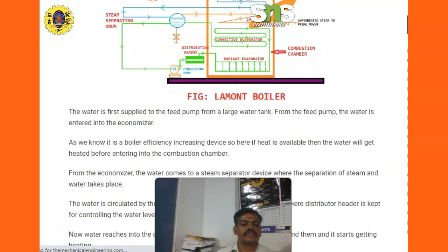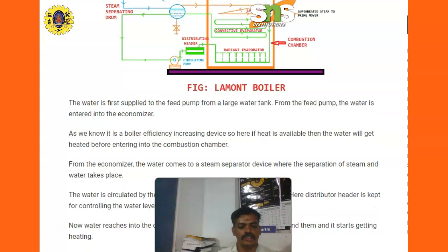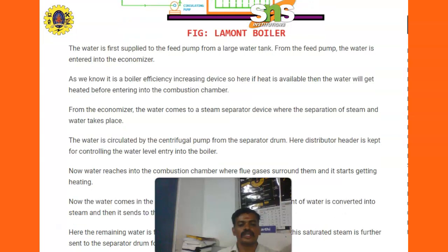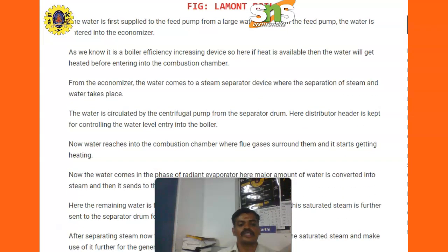The water is first supplied to the feed pump from the larger tank. From the feed pump, the water enters into the economizer — a boiler efficiency increasing device — where the feed water gets heated before entering the combustion chamber. From the economizer, the water comes to the steam separating device where separation of steam and water takes place. The water is circulated by the centrifugal pump from the separating drum. The distributor header controls the water level entering into the boiler. The water then reaches the combustion chamber where flue gases surround it and heating begins.